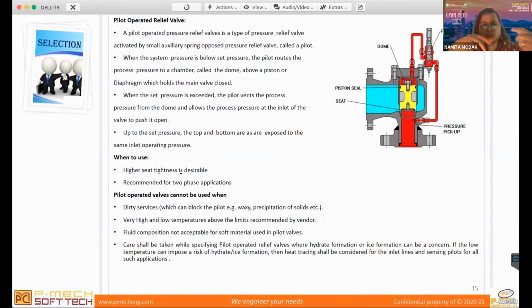Pilot operated is used when the back pressure to set pressure ratio is more than 50%. You will see there is one valve called the pilot valve here, and here is the main valve. Basically, in normal condition, your pilot is always experiencing the same pressure as the normal operating pressure of your system. During normal operation, the flow goes to the pilot and then to the dome. This is called the dome here. So basically, your pilot is balancing this valve. But once the pressure keeps on increasing and reaches the set pressure, what happens? The fluid in this dome goes out, and then this valve starts opening, and this is the outlet. So this is the way this pilot operated valve works.